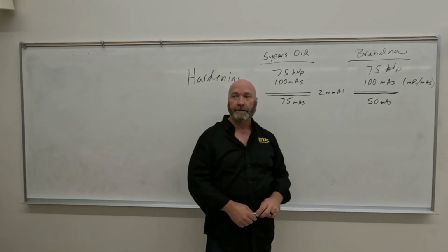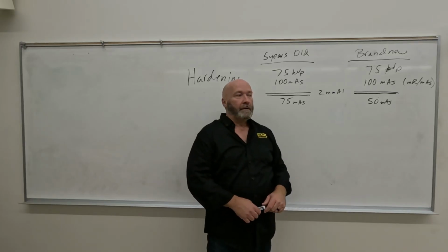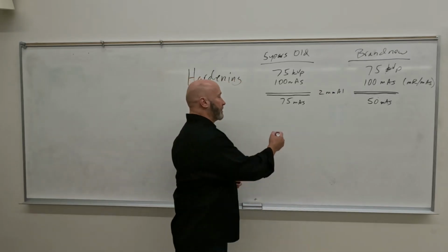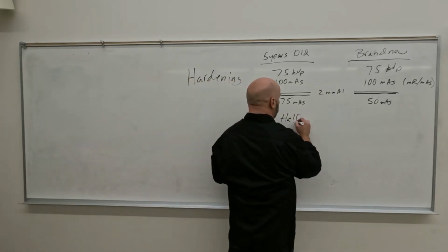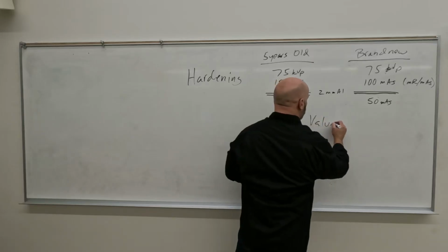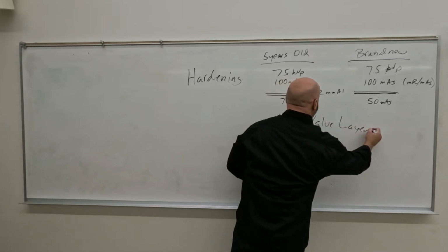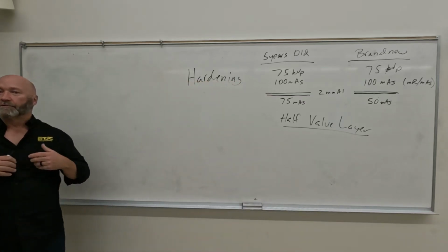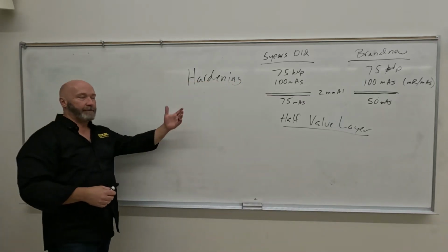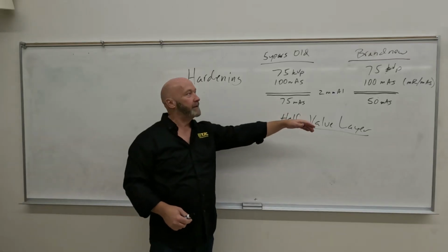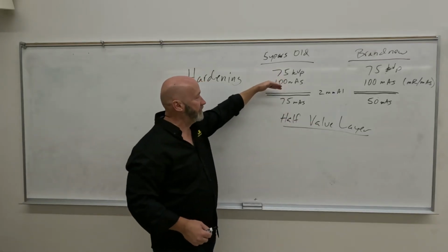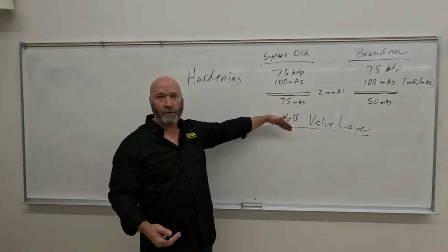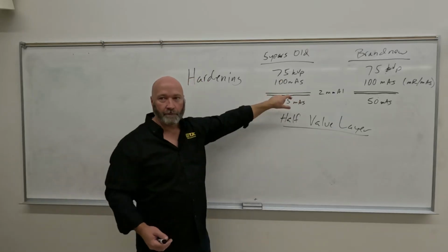It's a measure, still penetrated, but the better measure is what we refer to as half value layer. When you're talking about the true quality of the x-ray beam, yes, kVp factors into it. If I cut this down to 50 kVp, then this would be cut down to maybe 10 mAs post the 2 millimeters of aluminum.